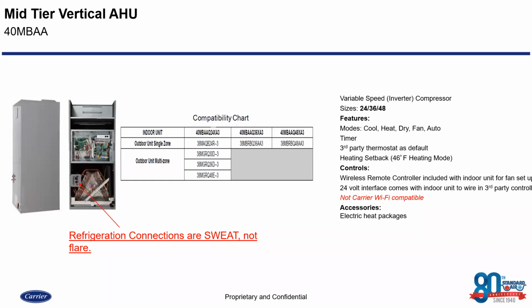However, what this does mean is if we're not using our press fittings and we don't have the room to get the press tool in there, or your company doesn't use press, when we are brazing, we need to make sure that we are flowing at least 1 to 2 psi of nitrogen in there to make sure that we're not getting that scale buildup inside of the pipe, which of course can clog strainers both at the indoor and the outdoor unit, which can create restrictions and of course individual zone or entire system failures depending on what type of configuration that you have.